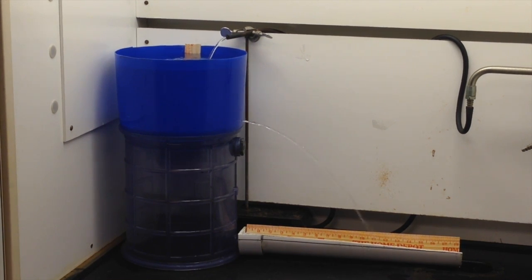Right now I've got the flow adjusted to 5 inches of pan depth to simulate optimal flow in a cooling tower, and what we're trying to demonstrate is that the lower the pan depth, the less the flow rate. So in this experiment, we see that going in the top at a certain flow rate produces a trajectory coming out of the hole in the bottom that hits the bottom ruler at about the 12-inch mark, 11.5 or 12 inches.